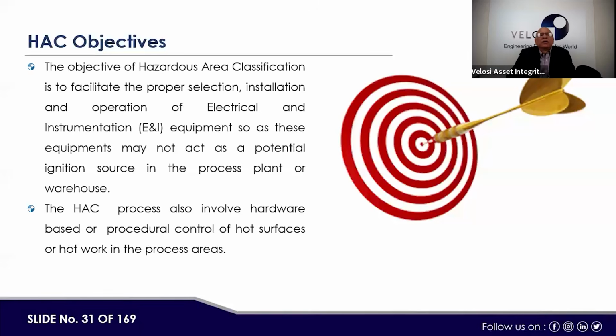Then HAC objective. The objective of hazard area classification is to facilitate the proper selection, installation, and operation of electrical and instrumentation equipment so that these equipment may not act as a potential ignition source in the process plant or warehouse. The HAC process also involves hardware-based or procedural control of hot surfaces or hot work in the process areas. As I said, it's not only electrical equipment, like a motor or a switchgear or a junction box or a cable termination point, or a transmitter or any kind of instrument available in the plant, that may act as an ignition source due to stray current, due to the voltage or due to the current available, or a spark might be created.